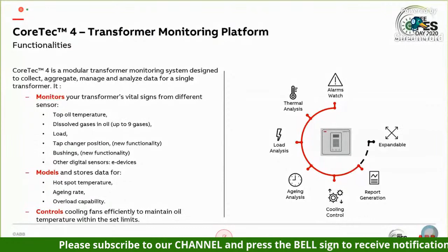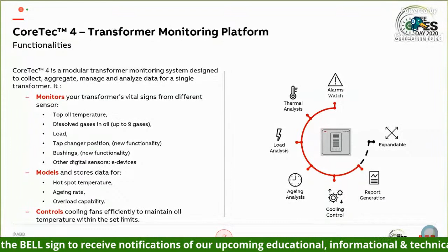The CoreTec 4 is a very modular transformer monitoring system. It is designed to collect, aggregate, manage, and analyze data for one transformer. And then if you have 50 transformers, you will have 50 CoreTec 4, all of them talking to APM. So CoreTec 4 basically monitors top oil temperature, dissolved gases, load, tap changer monitoring, bushing monitoring, and all the other devices. And it models and stores data for hotspot temperature, aging rate, overload capability. And it also can control the cooling fans to maintain the temperatures within set limits.